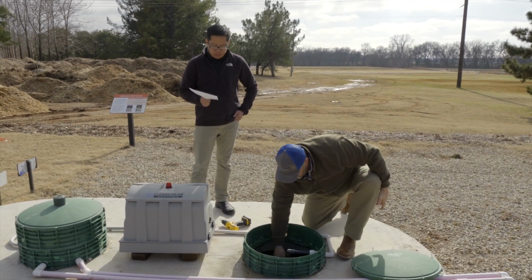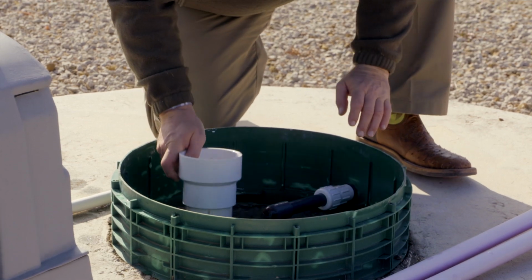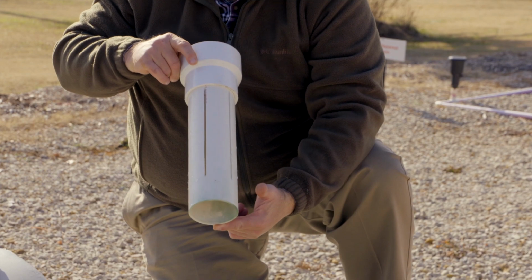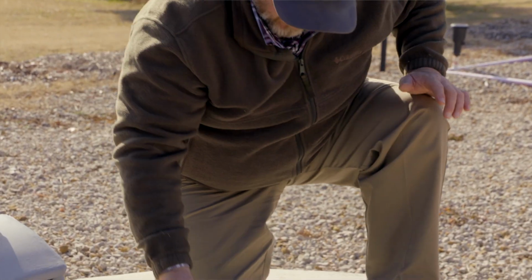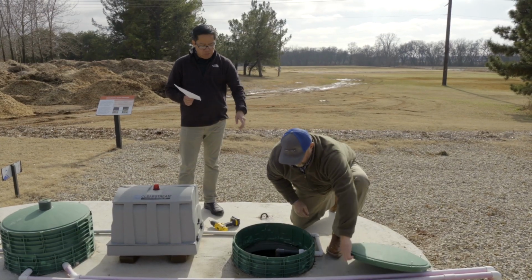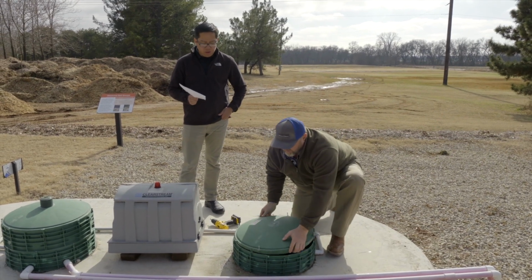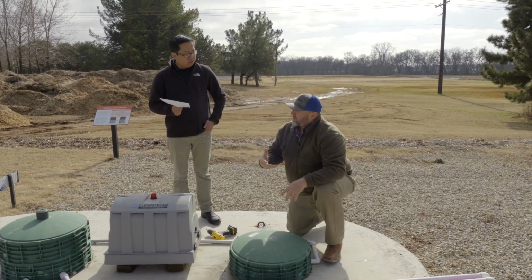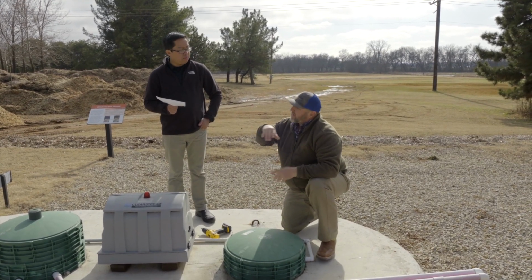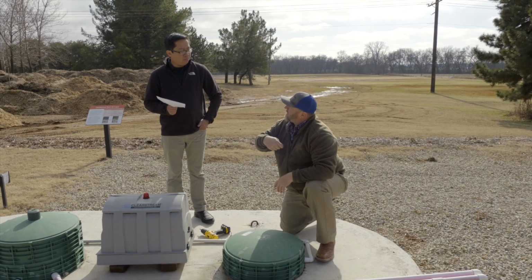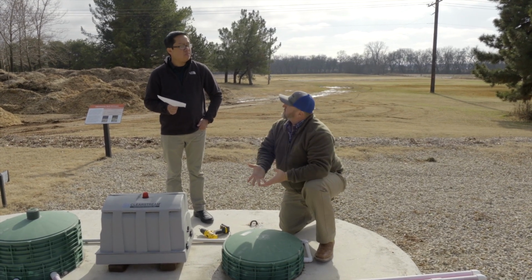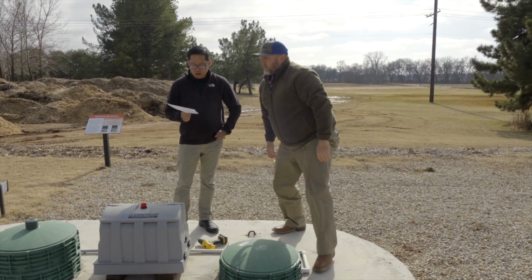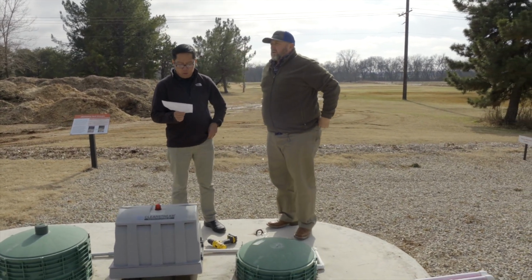You also have other components like your surge control weir. It could be stopped up and you could need to clean it. It's very rare, but you should at least look at it to make sure it doesn't need cleaning. So the diffuser and that weir are the key components. Inside the clarifier, in a good working unit, you'll also have a scum layer on top. If you break that up every 6 months, it'll drift back down and save you from having to pump it so often. Those two things are very important.